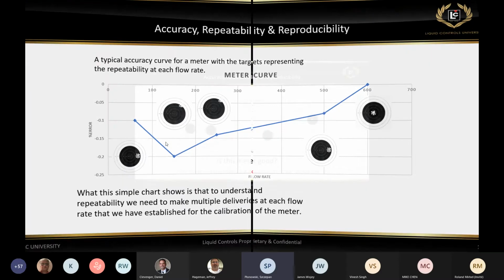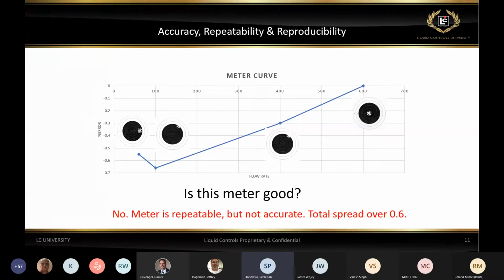Now, we'll look at a little bit of a different curve of a meter. Is this meter good? As you can see at the repeatability points, each point at each flow rate, those points are pretty repeatable. So that's definitely good. The meter is repeatable. It's definitely repeatable and accurate at high flow. But if you look at the overall spread of that meter between high and low, or one of the low points, this overall spread is a little bit more than 0.6%.